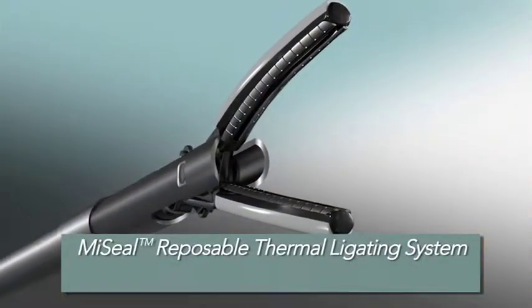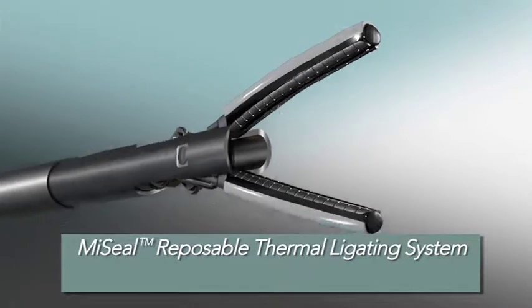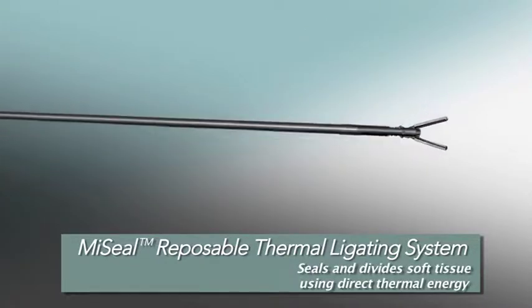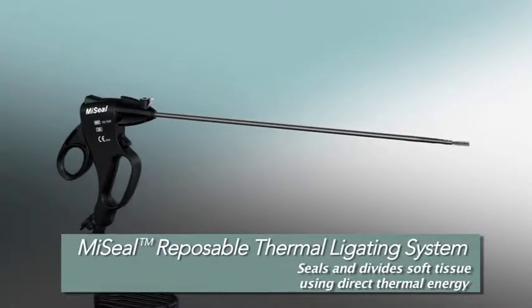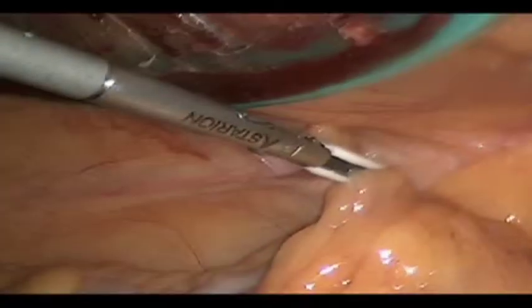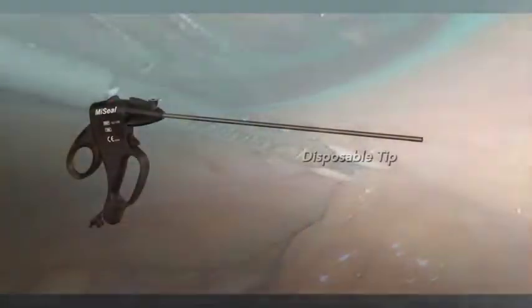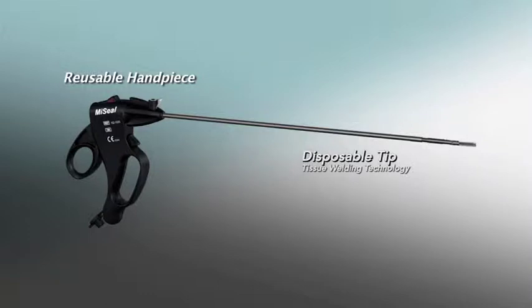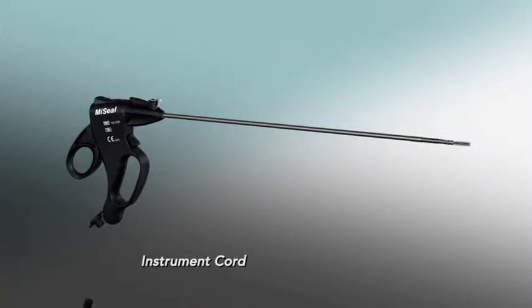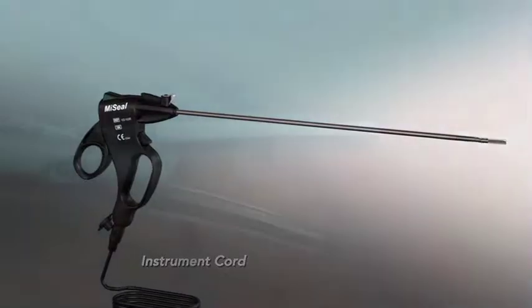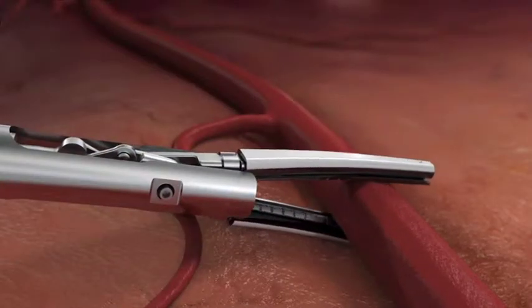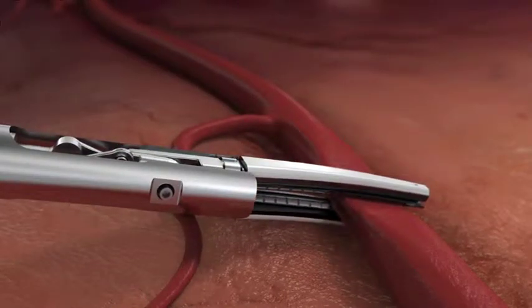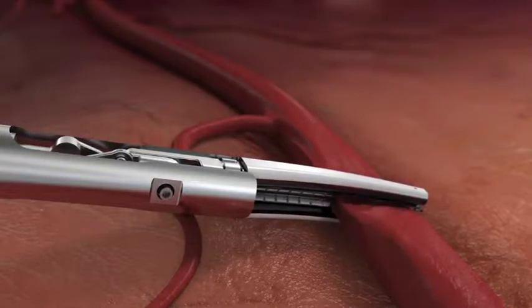Miseal is the first and only reposable device that simultaneously seals and divides soft tissue using direct thermal energy. The 5mm laparoscopic instrument consists of a reusable handpiece and disposable tip and cord. The device utilizes proprietary tissue welding technology to facilitate the precise application of heat, minimizing collateral damage.